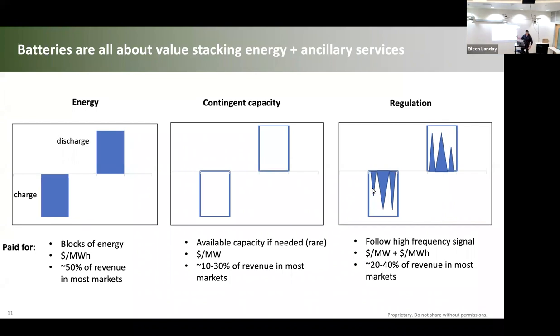And then there's this third category, which is called regulation. Typically in a lot of places people call it frequency regulation. That's actually not true because it doesn't necessarily have to be directly tied to frequency on the grid. It often is. But what's unique about the regulation market is that it's similar to contingent capacity - you get paid for the block of capacity you're providing, but the obligation is to follow a signal that is not obviously known. So you have to interconnect with some kind of third party that's sending you a signal for what you should do at any given time. That signal is typically going to be greater than zero, so you're going to do something over that period, and it's typically a high frequency signal. People refer to it as AGC, automatic generator control, and it's typically like 4 seconds or something like that.